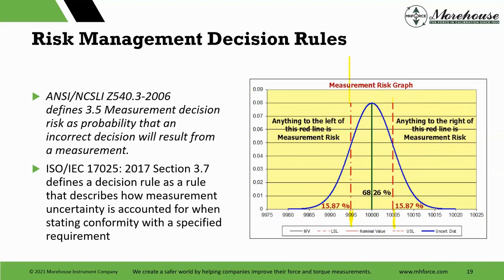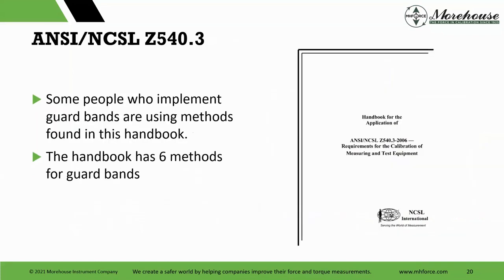When we take into account measurement uncertainty, the measurements we make can have a large portion of that normal distribution hang outside of the specification limit. And in this case, this would be your conditional pass situation. Is it okay? Is the customer okay with 30-some percent risk in this scenario? I don't know. That's where ILAC G8 comes in.